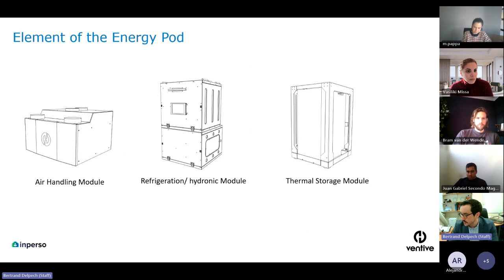So the 3 sections look like this. The air handling module on the left is taking care of all of the circulation of the air in the property. Then the refrigeration and hydronic module, which is the heart of the heat pump, really. It has the compressor, the control system, and all of the water circulation system, pumps, valves, etc. And then finally, the thermal storage module, which is basically a large square with a PCM inside. This is where most of the weight of the system is.